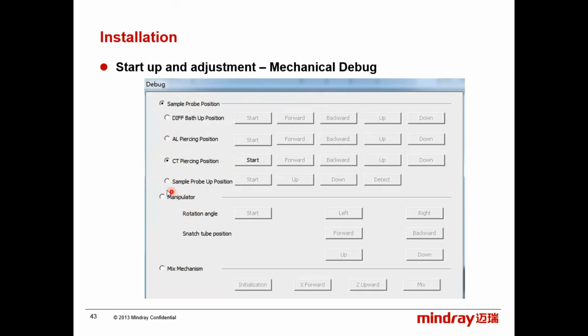This is for the manipulator also. It's very important. The manipulator is the gripping of the mixer. It is the part that grabs the tube and mixes it. This one also needs to be perfectly centered. Otherwise, when you install it, if you do not check it, after 1 week maybe or 10 days, one of those two metallic parts of the gripper will break. Because each time it grabs the tube it is not centered, it will hit the tube till it breaks. All right? This is for the mix mechanism self-test. You can initialize it, move it in the X direction, in the Z direction, mix sequence, and so on.